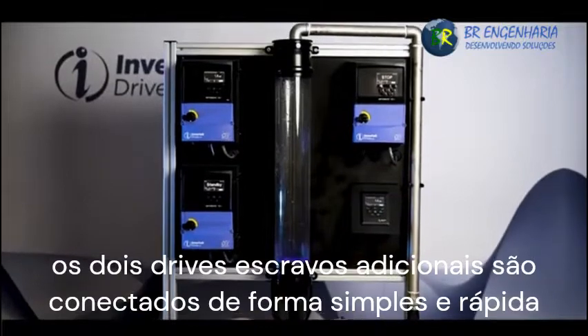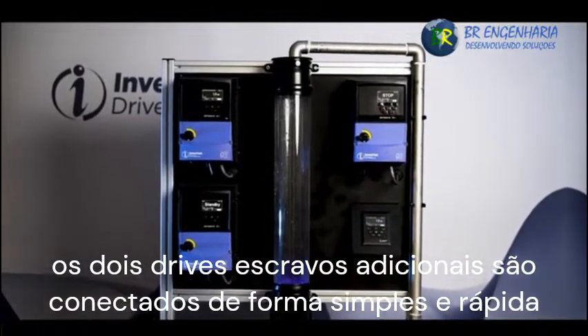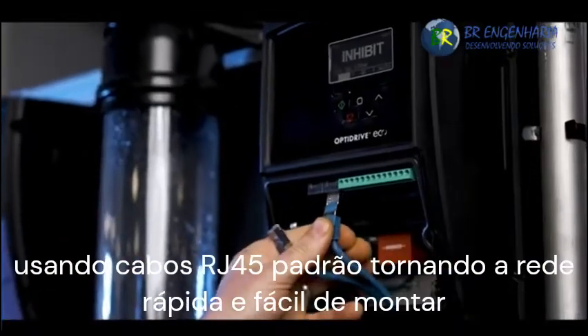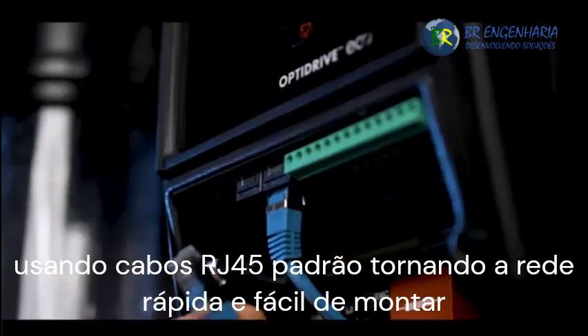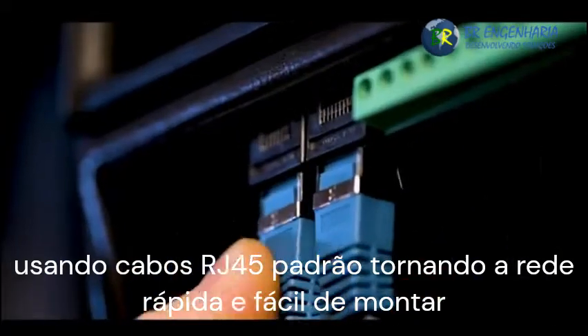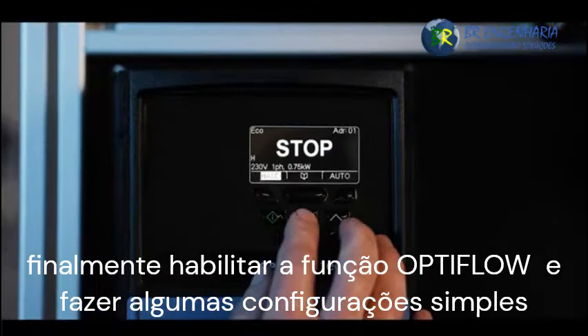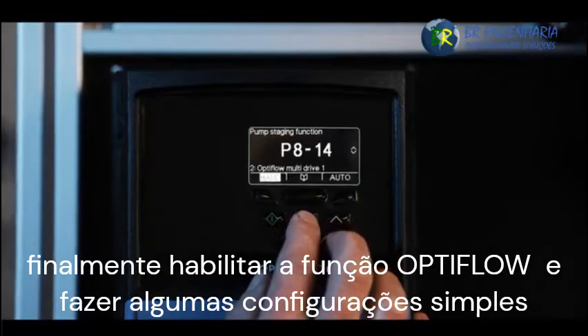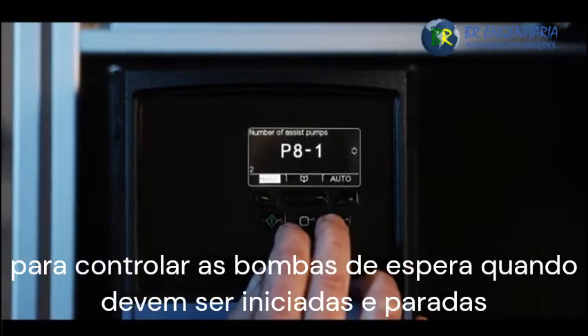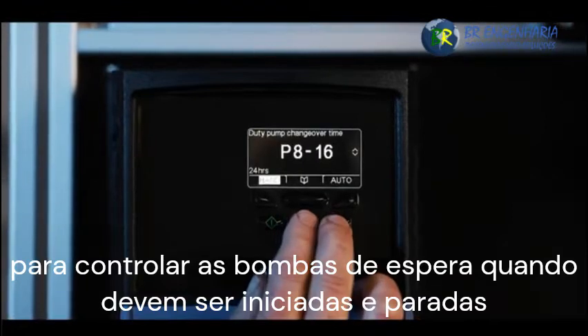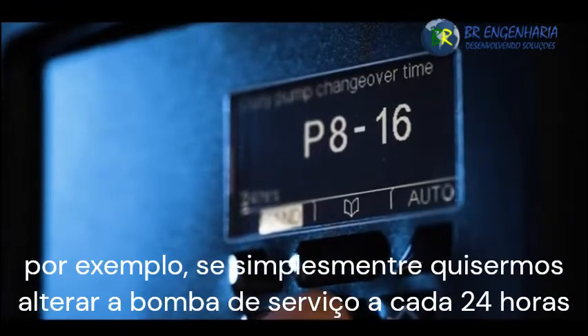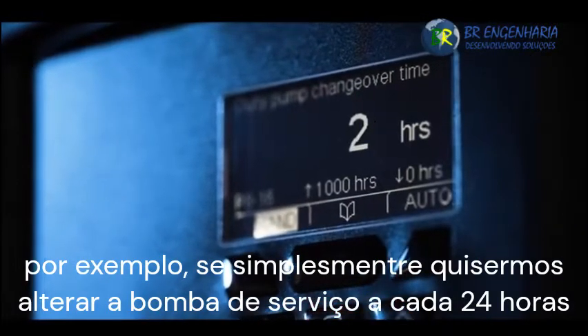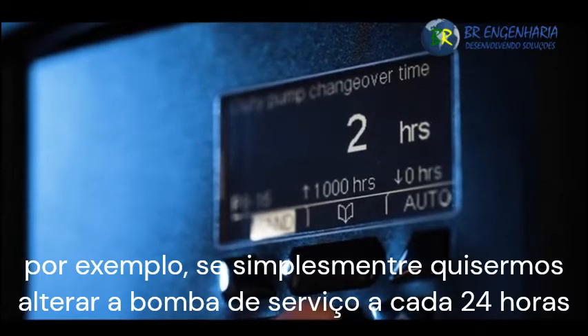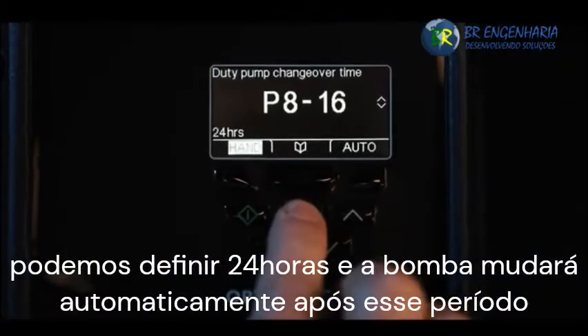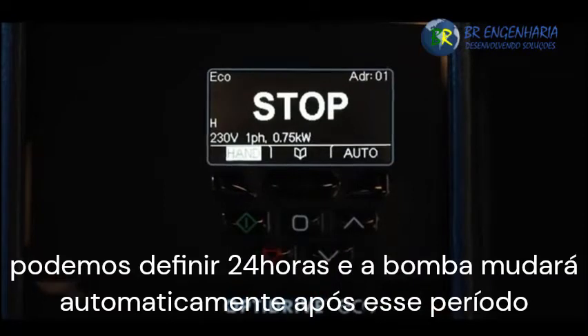The additional 2 slave drives are simply and quickly connected using standard RJ45 cables, making the network very quick and easy to assemble. Finally, enable the OPTIFLOW function and commission some simple settings to control when additional pumps should be started and stopped. For example, if we simply want to change the duty pump every 24 hours, we can set 24 hours here, and the pump duty will automatically change over after this time.